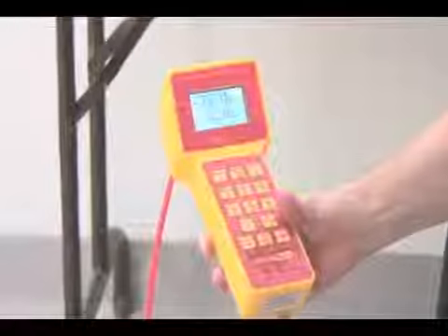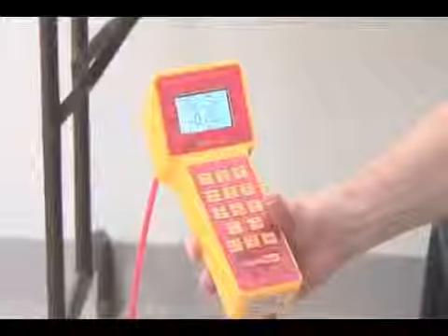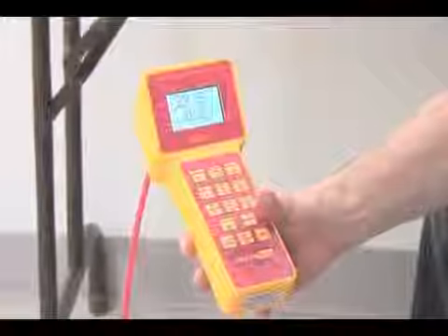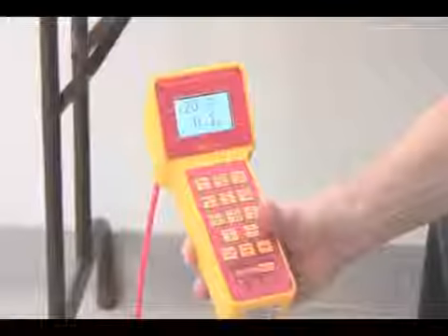Now, if I put it on the inlet side where I have a suction pressure, which would be equivalent to the downwind side of the house, I have a big negative pressure there. So we can see that the wind has a huge effect on the reading on our gauge.